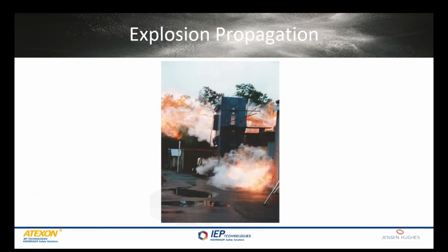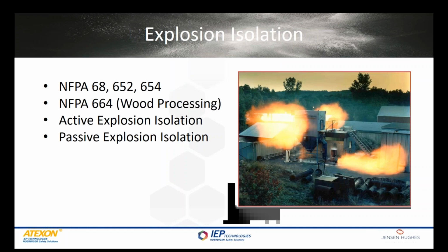Regardless of whether you're using explosion venting, flameless explosion venting, or explosion suppression at a process vessel in a biomass facility, these vessels are fed from somewhere and typically discharged somewhere. If there's not an adequate mechanical barrier in between vessel A and vessel B, that flame can propagate. And the propagating explosion can create some very, very high ignition energy sources which would result in the secondary or the connected vessel having a much more dynamic explosion than the initial one if that explosion propagation is not caught. As a result of that, NFPA, in a number of different standards, has specific requirements for the use of explosion isolation. That means to stop that flame from traveling from one vessel to another.